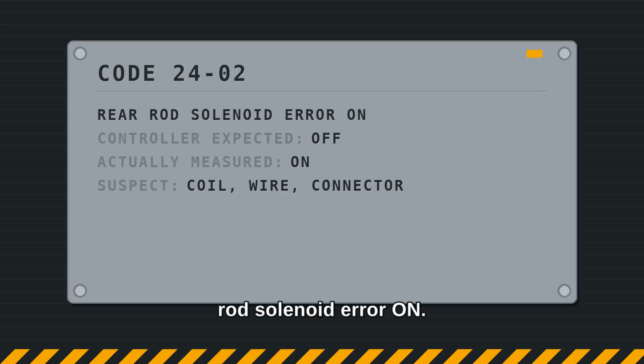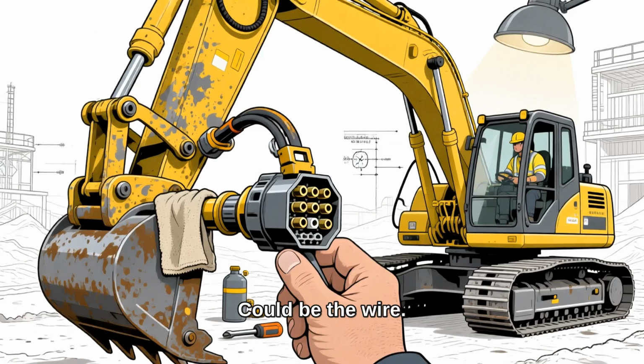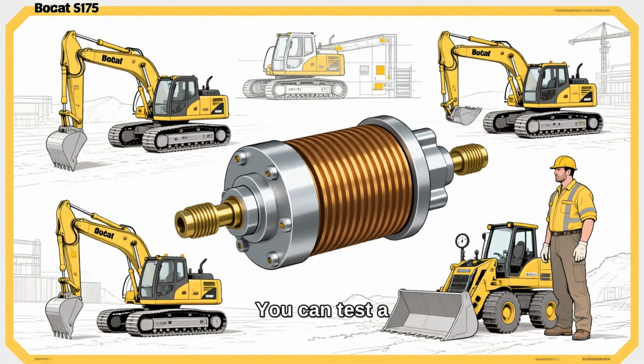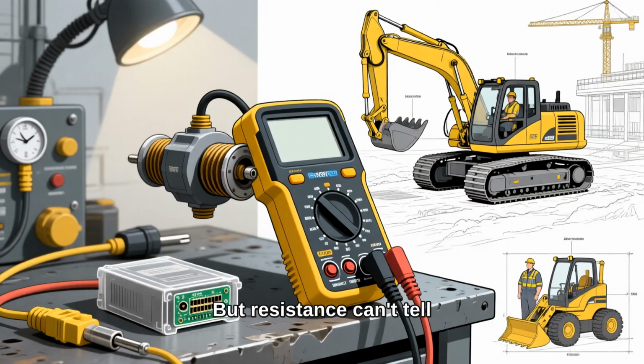24-02 is rear rod solenoid error, ON. It means the controller expected one state and measured another. Could be the coil, could be the wire, could be the connector that's been packed with dust since spring. You can test a coil with the meter alone. Resistance tells you whether that winding is still in one piece. But resistance can't tell you whether the controller ever sent the command. That's a completely different question.